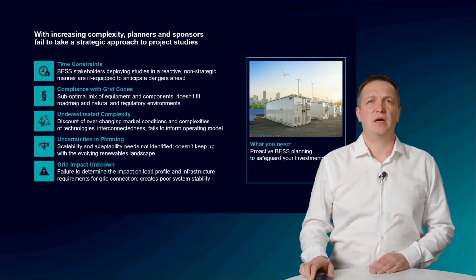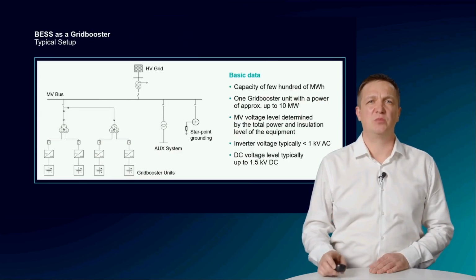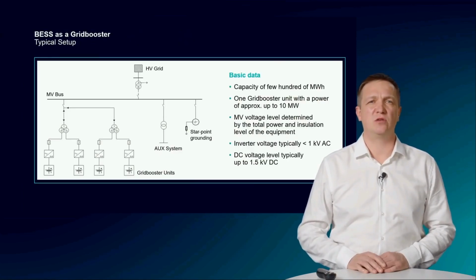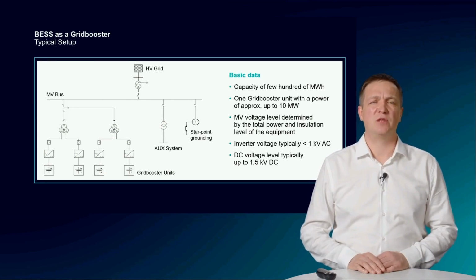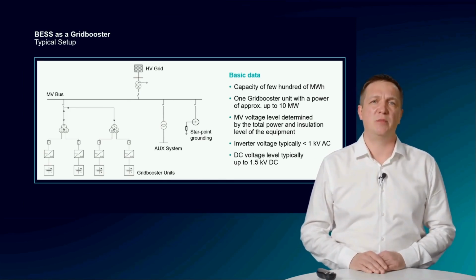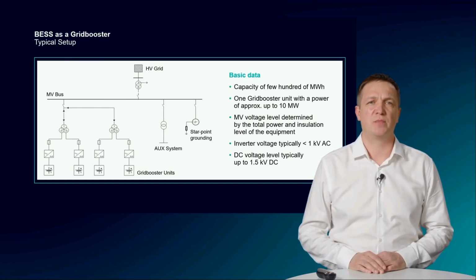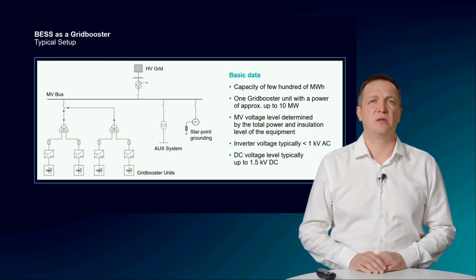We as PTI are involved in the largest grid booster project worldwide to be installed in Germany. In this project, we are responsible for performing different energy studies and checking the dynamic and transient performance of the grid booster. As the name suggests, the grid booster provides a rapid response triggered on demand by the transmission system operator. We could compare the principle of a grid booster to a conventional turbocharger in a combustion engine. It is there, but it steps in only if additional power is required.